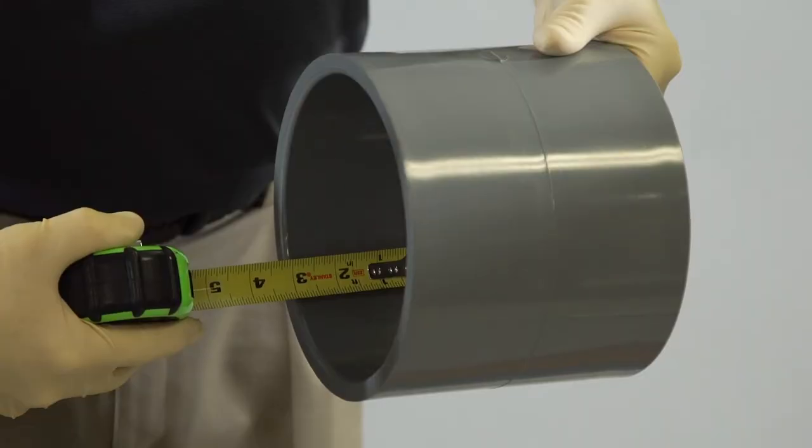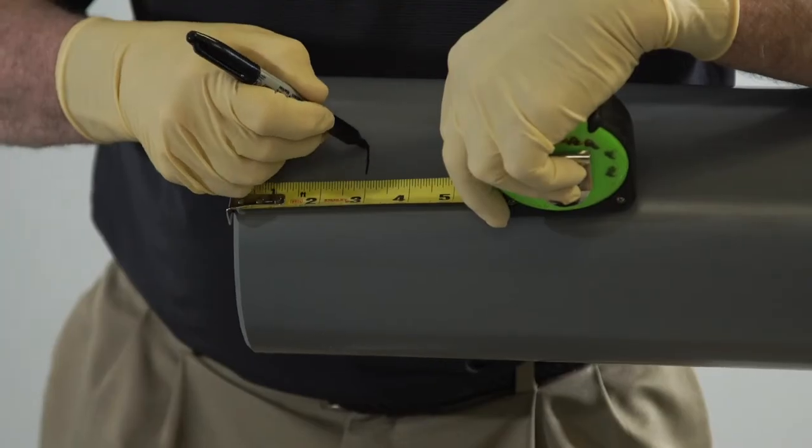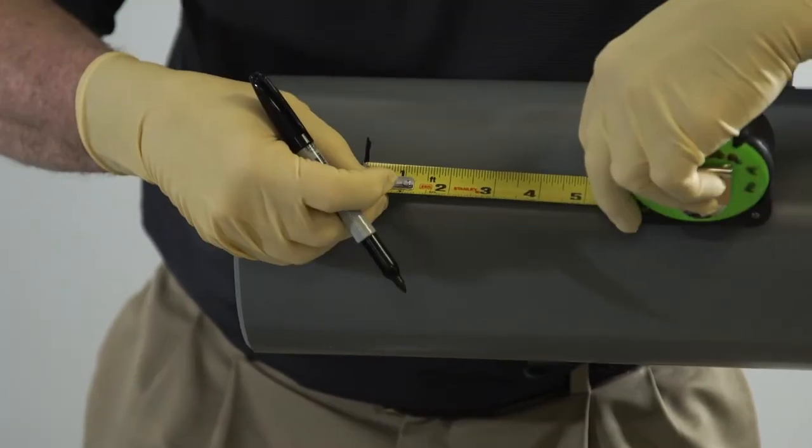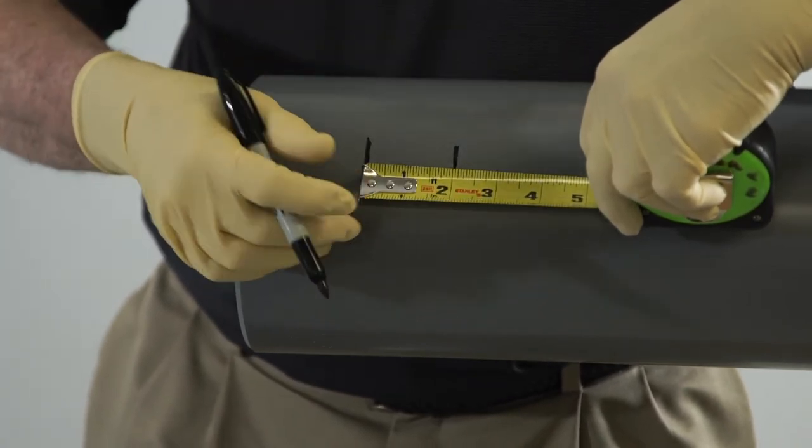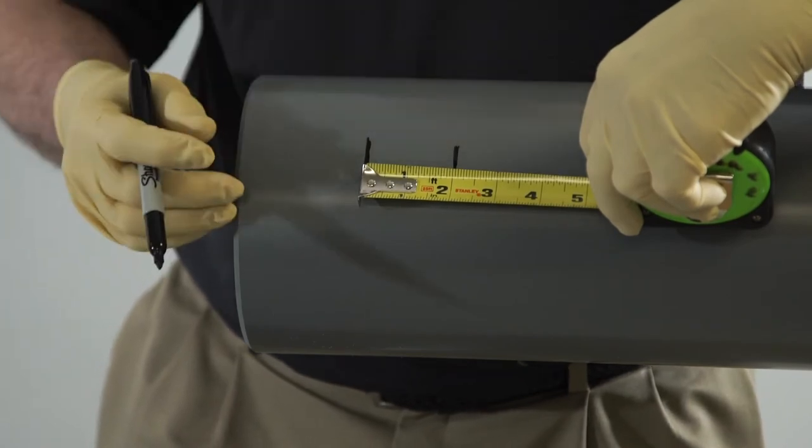Measure the fitting socket depth and mark the distance on the pipe OD. Add two inches to this distance and make a second mark on the pipe OD. The first mark should be covered during the application of both primer and solvent cement.